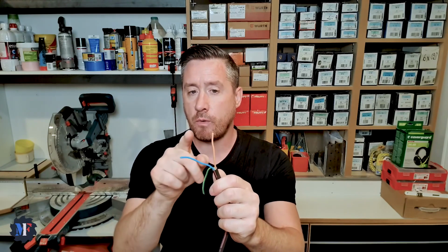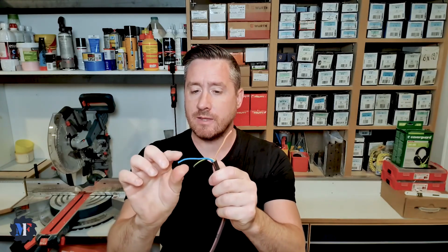It's always blue, you don't use yellow and green for the neutral, and you don't use orange or red either. It stays blue, that's mandatory. Yellow and green are for ground, blue is for neutral. For the hot wire, you use brown, black, orange, red or purple if you want. You can do whatever you want with the hot wire.